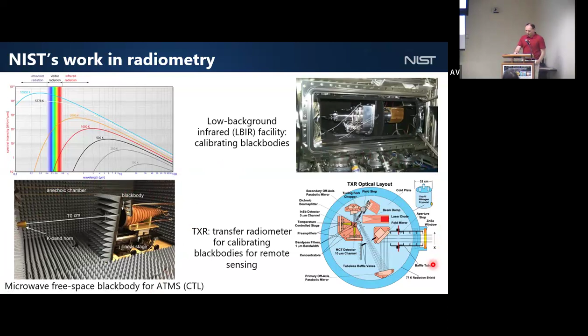So NIST has blackbody sources that are optimized for calibrations in the microwave regime, ones that are optimized for low temperature. If you have something that you need calibrated, but you can't send it to NIST, we have a transfer radiometer that can be sent to wherever you have a device that needs to be calibrated. So NIST has done some work in the past with, for example, the CoBRAS instrument, which is manufactured at L3 Harris. And so at the Harris facility, they have this external calibration blackbody, external calibration target that they use for calibrating, and they want to have some sort of validation that their calibration is correct.